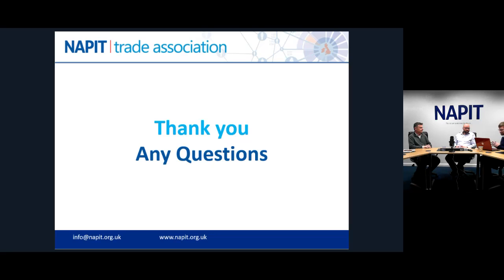Yeah. This one sort of also follows on a little from the RCD stuff we touched on in the previous webinar. So if this is something that we can't get through entirely now, we'll get an answer later on and we'll pop it up on the NAPIT forum. But to do with RCD selectivity, we've previously talked about requirements for upstream RCDs to be equal to the type of downstream ones. So does this mean the generator RCD or the ISU RCD should be a type A, F or B type time delay unit to allow for the inclusion of new RCDs downstream?